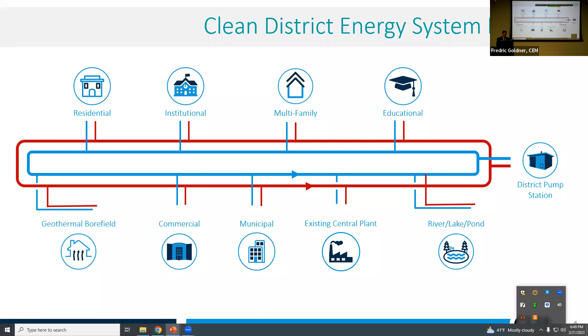Because BTUs is nothing more than the delta T across the volume of water we're pushing, we will gradually realize people are using less energy from the loop, the delta T drops, and we'll start to slow down circulation to maintain that delta T. 50 degrees is the temperature you'd like for heating, when we're making the loop colder, and 90 degrees would be the upward temperature during summer for cooling, when we're putting heat back into the loop. Did that answer your question, sir?